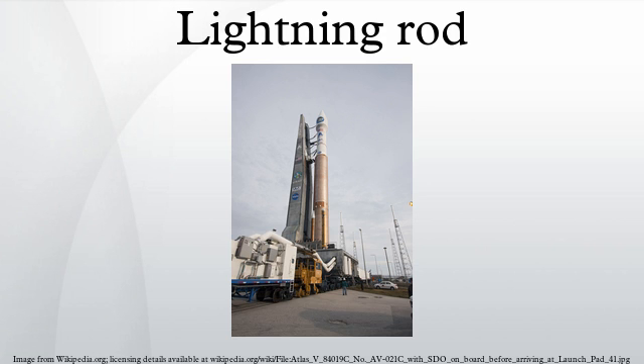The National Fire Protection Association provides a risk assessment worksheet in their Lightning Protection Standard. IEC Lightning Risk Assessment comprises 4 parts: loss of living beings, loss of service to public, loss of cultural heritage, and loss of economic value. Loss of living beings is the most important, and this is the only loss taken into consideration for many non-essential industrial and commercial applications. IEC risk assessment calculations can be very complicated unless done by a software.